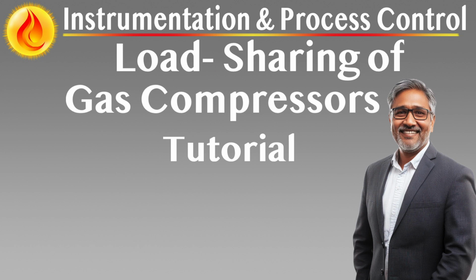1. Compressor network moving away from surge. The unit with the highest recycle valve output, i.e., most open, begins to close its valve faster. The other units slow down their valve closure rates. This prevents premature exit from surge protection in some units, while others still require relief.